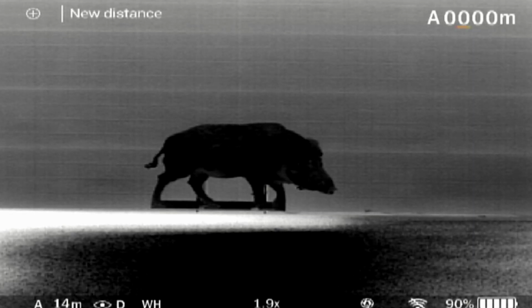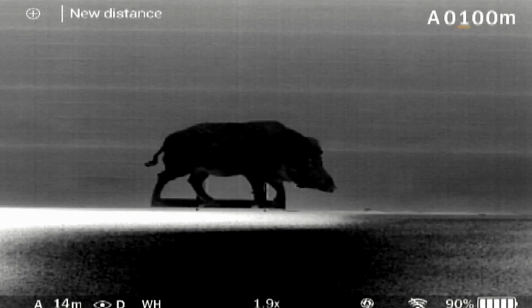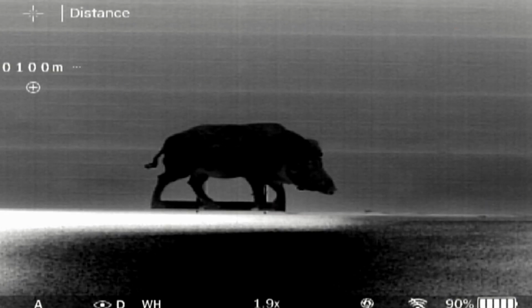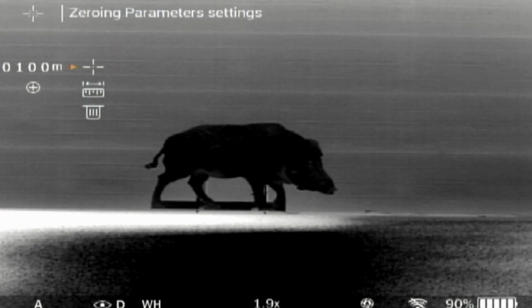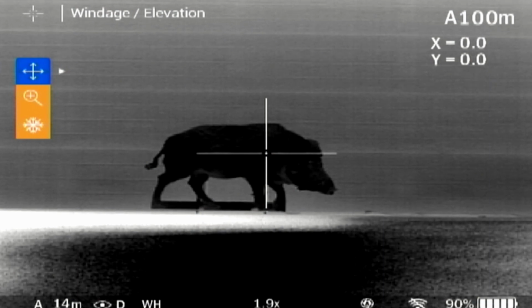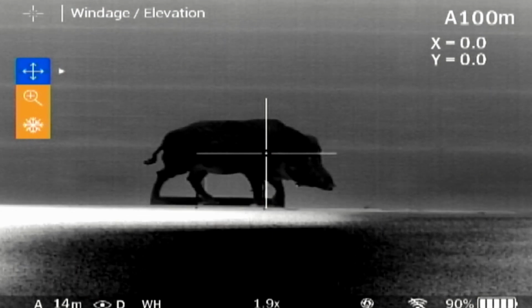Set the value for each digit with the up and down buttons. Switch between the digits with a short press of left or right button. Press the middle button to save the new distance. Press right to select the distance. Then press right again to jump into the zeroing parameters setting.